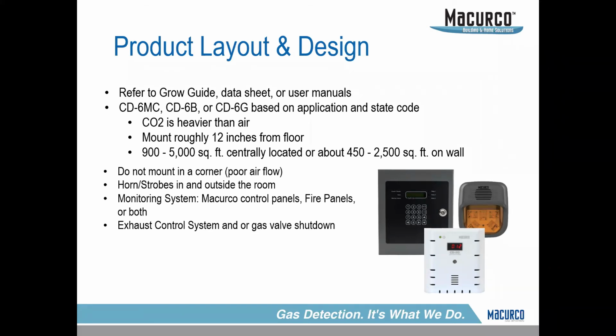So this comes down to the product layout and design. If you know what's happening with the detectors out in the field as a technician or as a technical support specialist, let's call it that, you can kind of get a good feeling on how these things are laid out and what it starts to look like. So we've all kind of gone through this process of being technical support to a product layout and design. What I mean by that is if somebody gets a spec and it's a design build, or an engineer maybe overspec'd it and put in an extra 15 detectors where it wasn't needed, or maybe is missing a gas - we'll do our best to catch most of that.